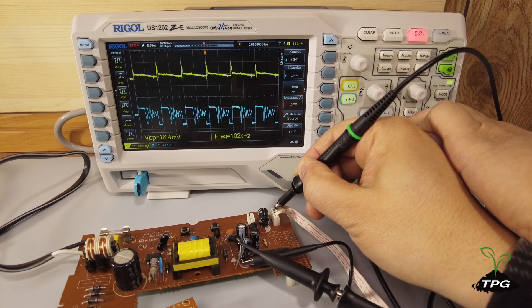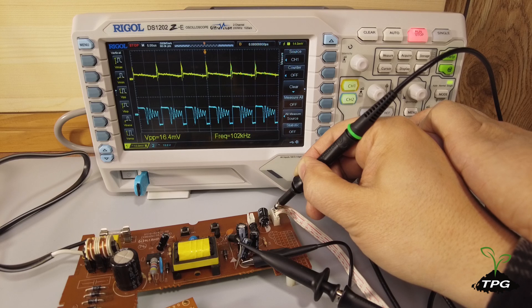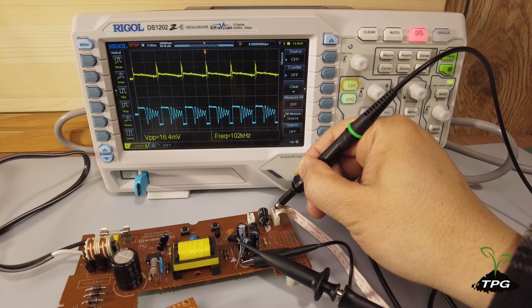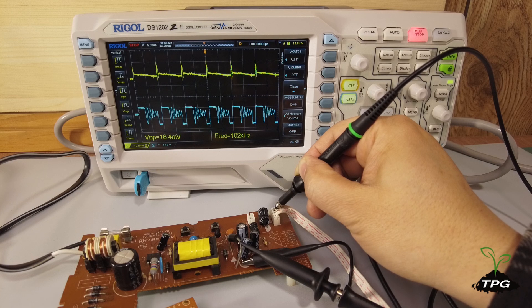Typically the ripple voltage should be less than 0.5 percent of the output voltage. In this measurement it is approximately 0.32 percent of the output voltage.